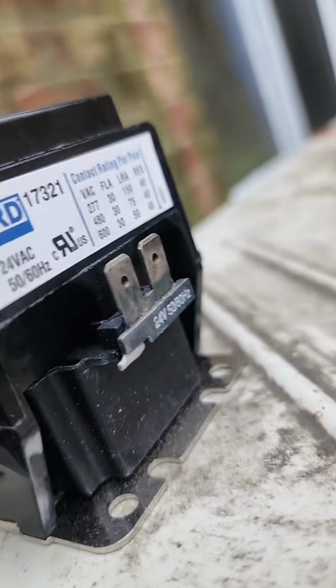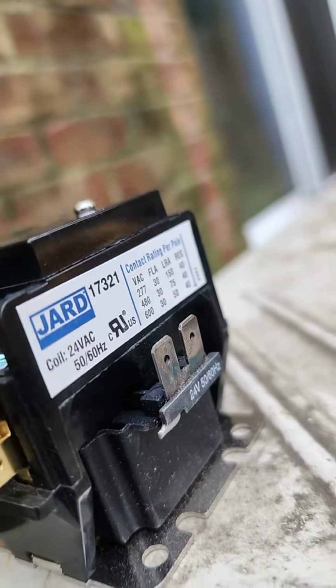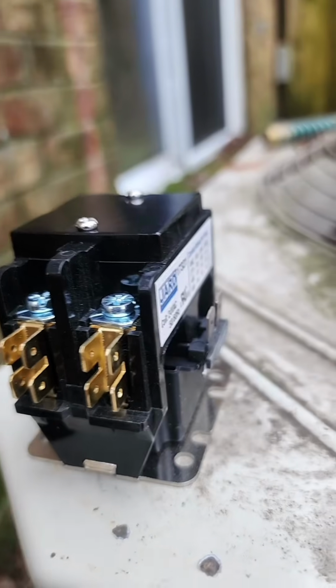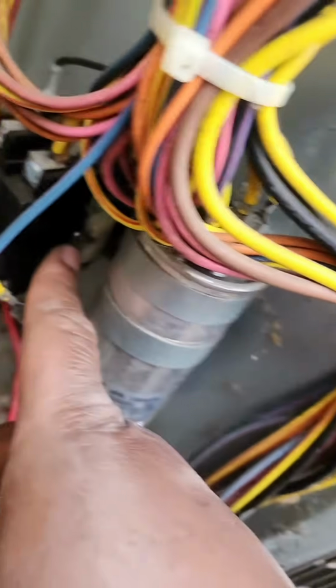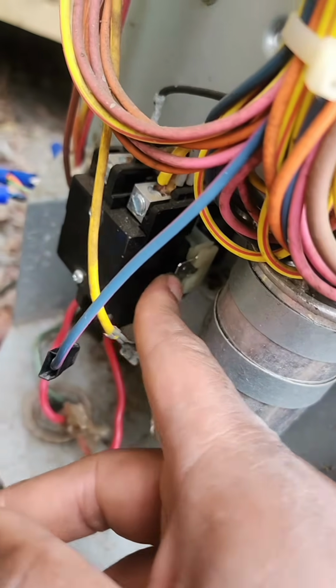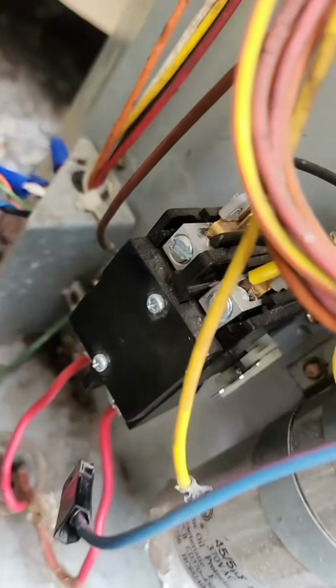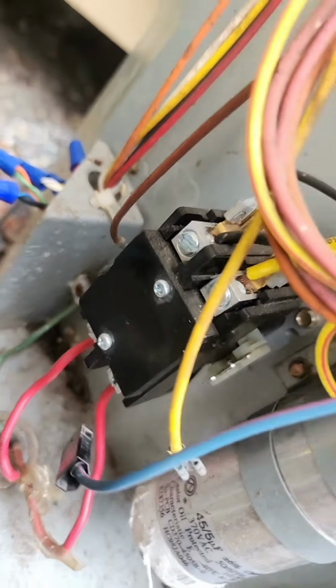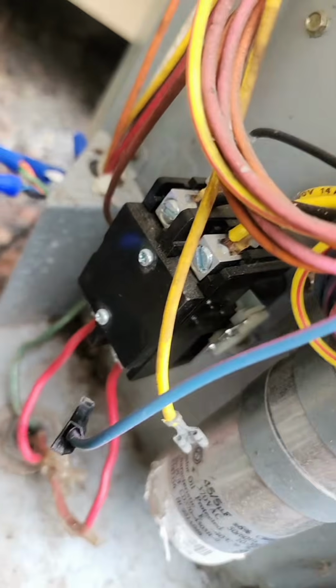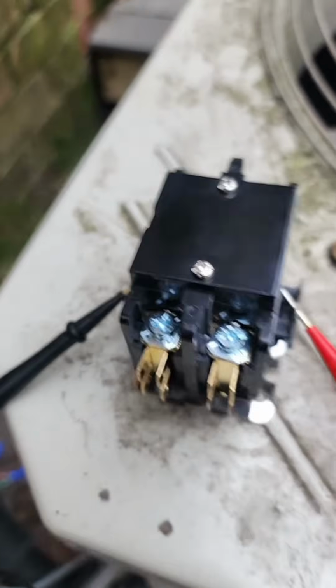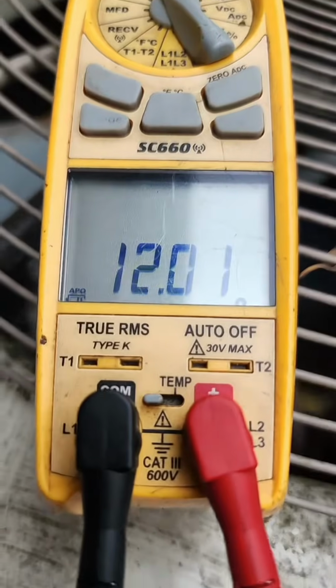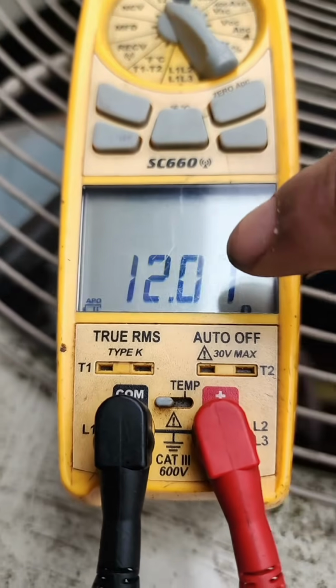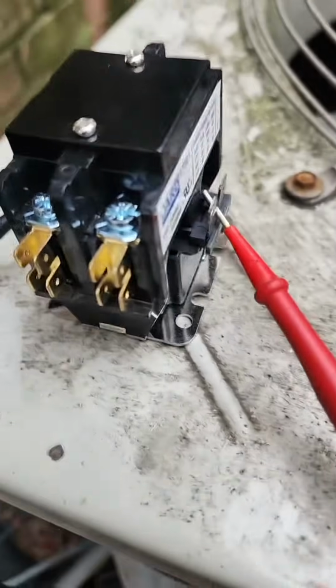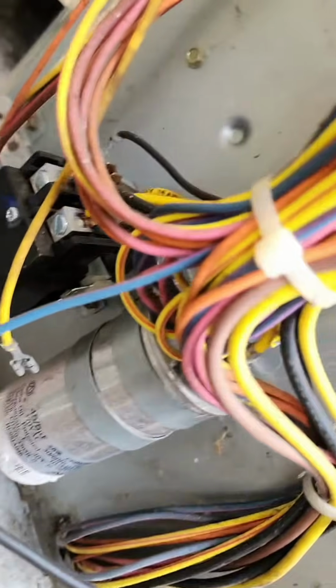Alright, so when you're checking the contactor coil resistance, you should get between 10 and 20 on the resistance. That's how you know you got a pretty good coil. Those are textbook numbers. This one's getting me 0.6, which means it's shorted to ground. My phone blowing up. So yeah, we'll pop another one in here. We should be good. Alright, so this is the new contactor. You can see between 10 and 20 on the resistance. So you know that's good. So watch once I hook this one up.